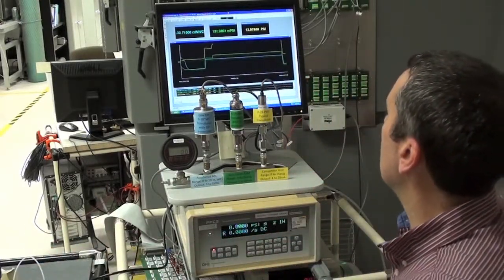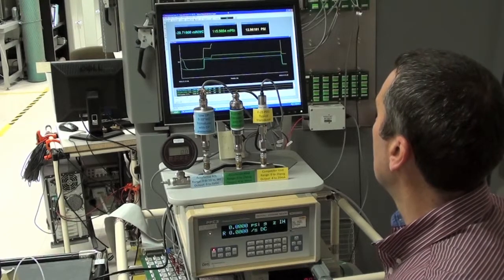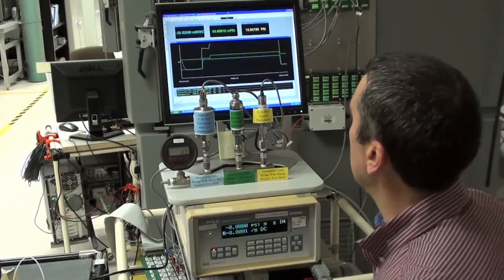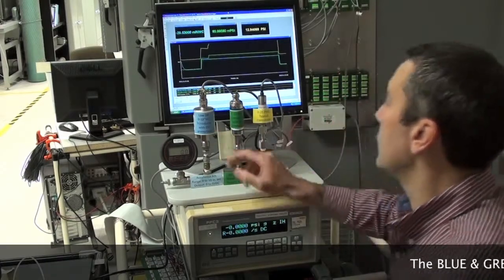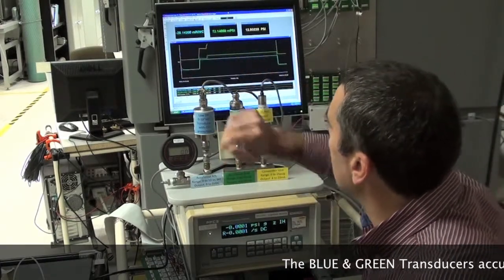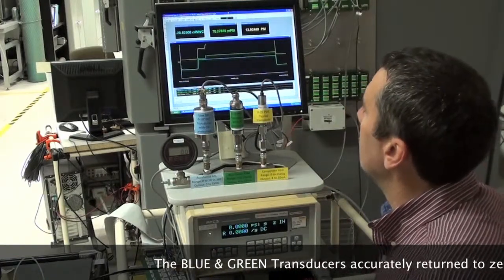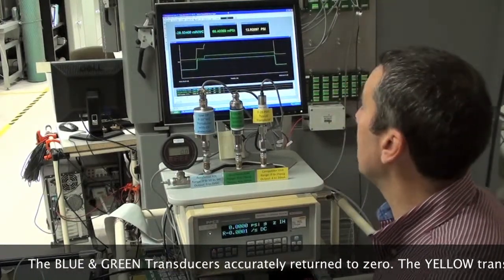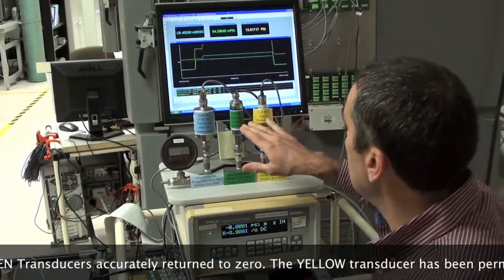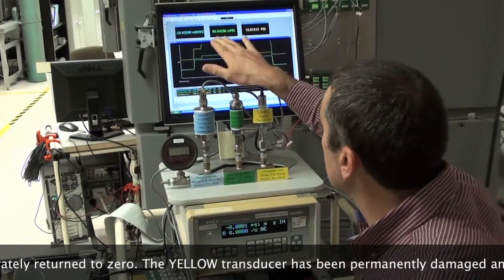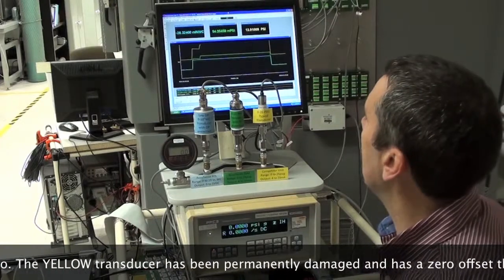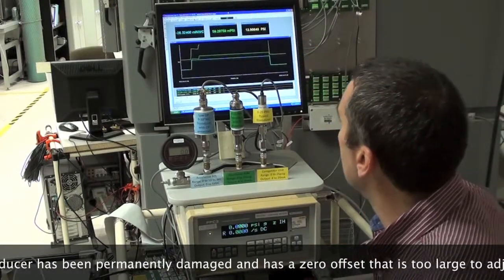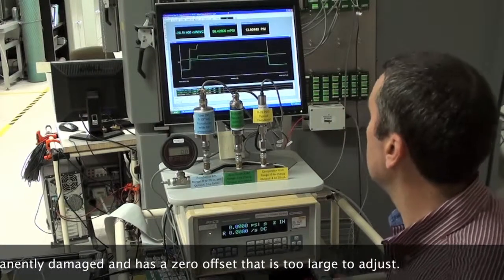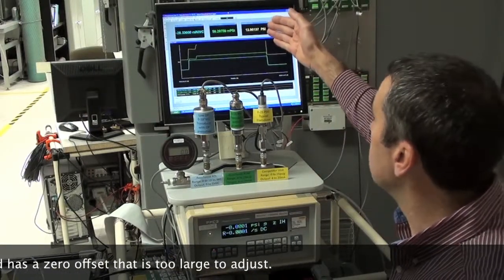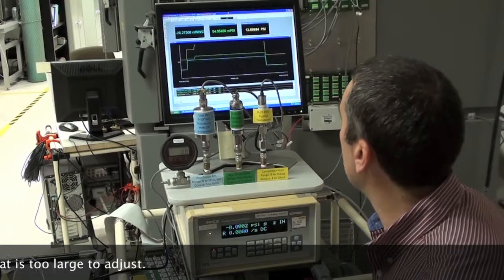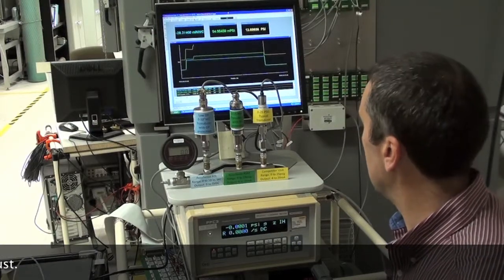Now we're returning to 0. Very easy to check. The manifold is vented. The low differential pressure transducer is reporting in the milli-inches of water. So it's a very negligible effect on the 0. Same with the 15 psi-G, that's reporting 60 milli psi. Again, it's recovering pretty good back to 0 where it started. This one had already been proofed, and it looks like it just continued to go in that same direction. It's closer to 13 psi now.